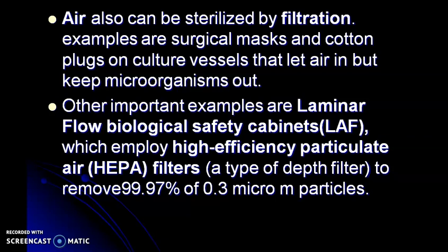These safety cabinets force air through HEPA filters and then project a vertical curtain of sterile air across the cabinet opening. This protects a worker from microorganisms being handled within the cabinet and prevents contamination of the room. These are employed in research labs, pharmaceutical industries, or anywhere a sterile working surface is required, where we have to employ a LAF.